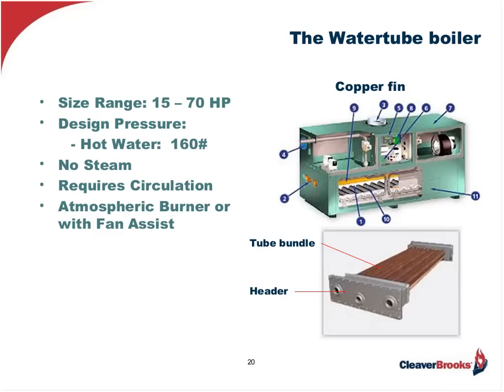The copper fin boiler evolved primarily for pool heating but is now used extensively for commercial building heat. The size range is small, and these are normally applied as multiple units with a control sequencer used to stage the firing based on system demand. The tube bundle is normally copper, but copper-nickel is also available if water conditions dictate, and the headers can be either cast iron or bronze for the same reason. Copper fin units require forced circulation and normally employ an atmospheric gas-fired or fan-assisted burner. Note that these units cannot be used for steam — only hot water heating.